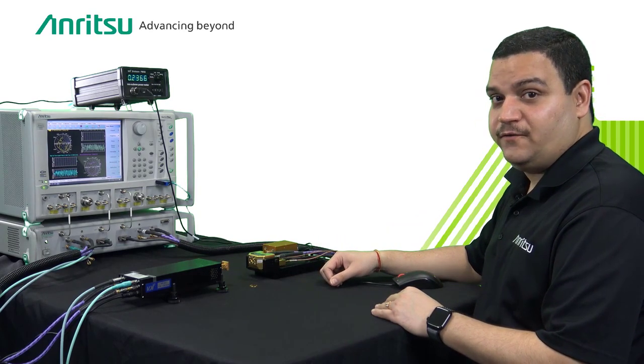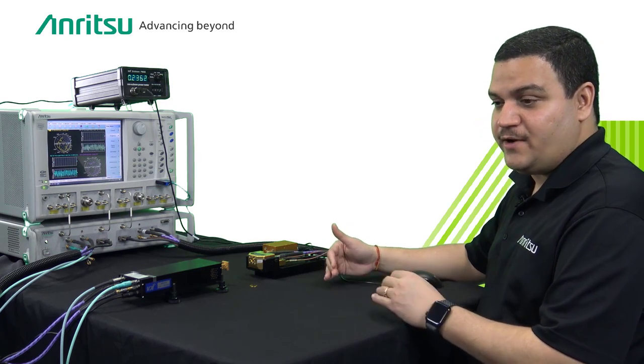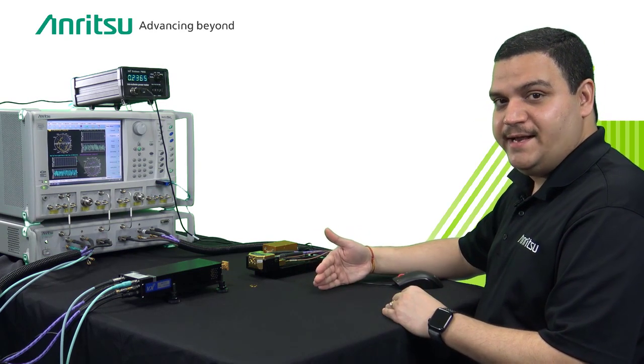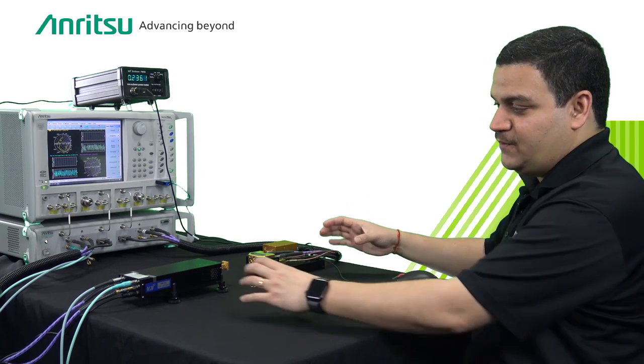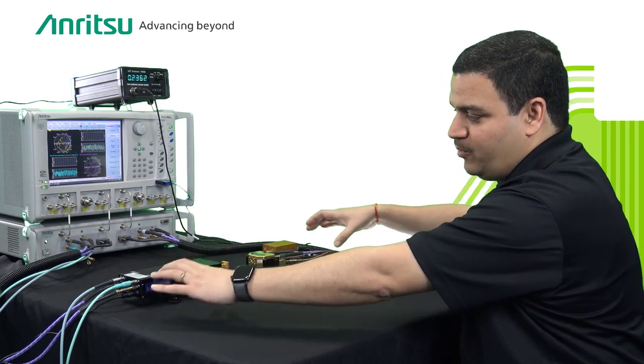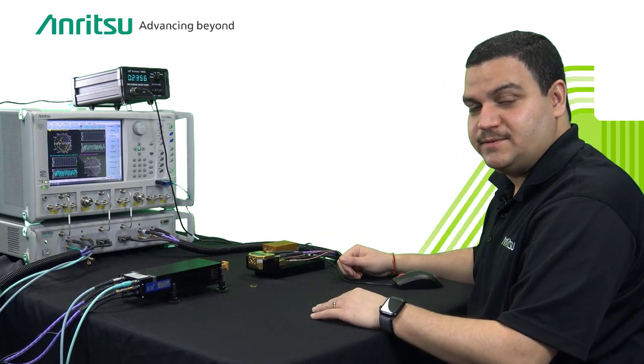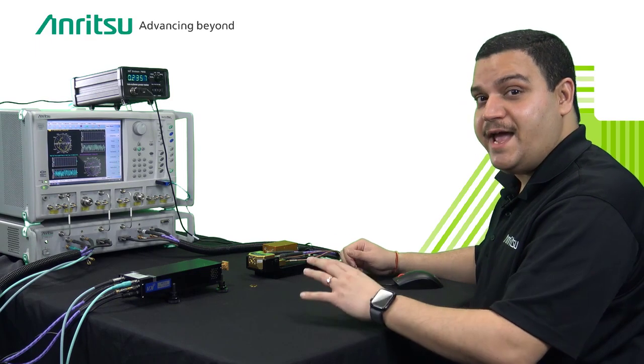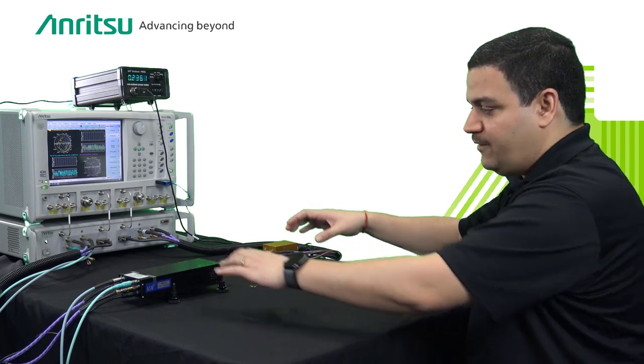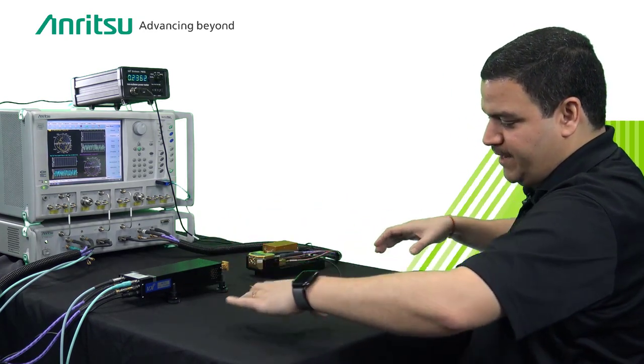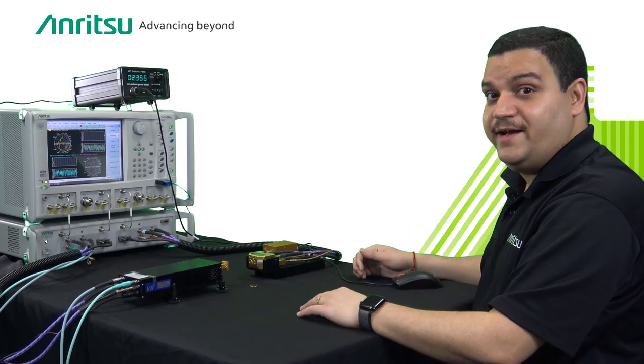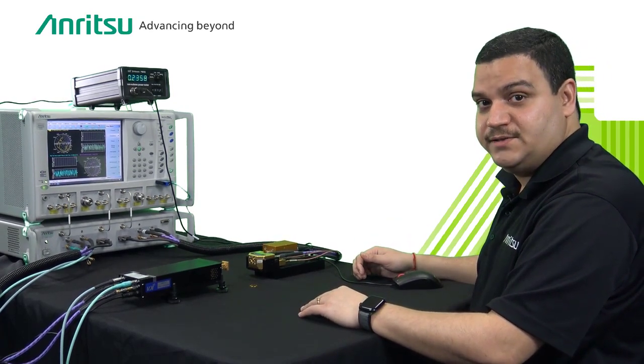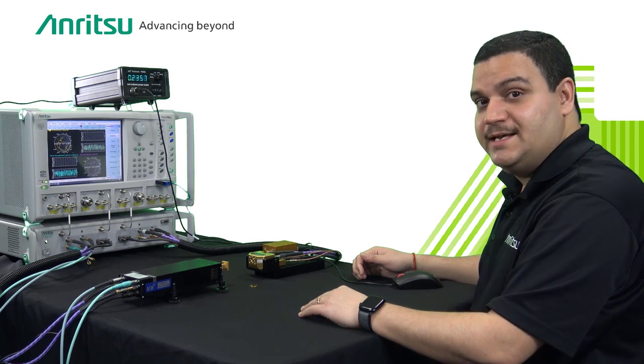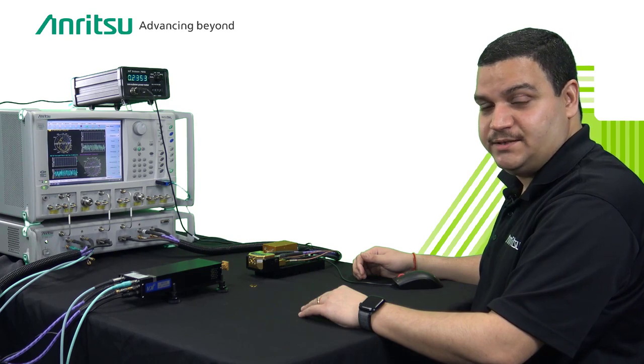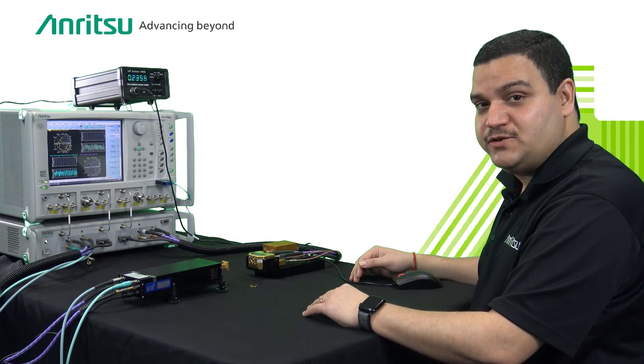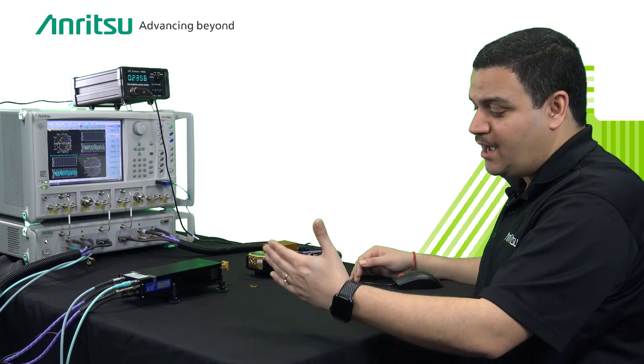Now, the challenge with a lot of customers has been that for, say, characterizing devices in E band, W band, D band and G band, you need to have two of these VDI mmWave modules on both sides to make waveguide banded measurements, which means you need to have 8 of these VDI mmWave modules covering E band, W band, D band and G band. That is a very costly solution, and there are a lot of challenges for doing calibration, repeatability, calibration accuracy and measurement stability.